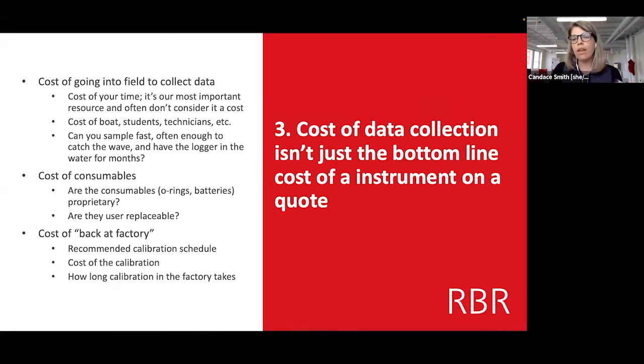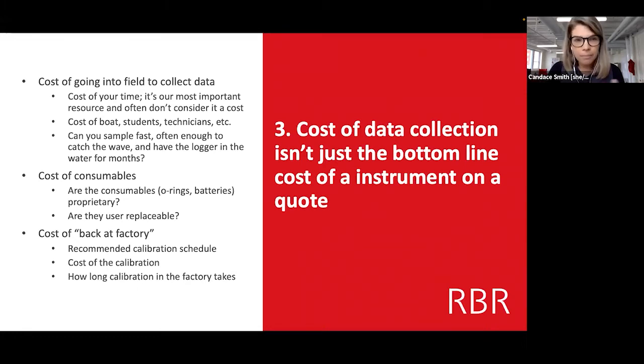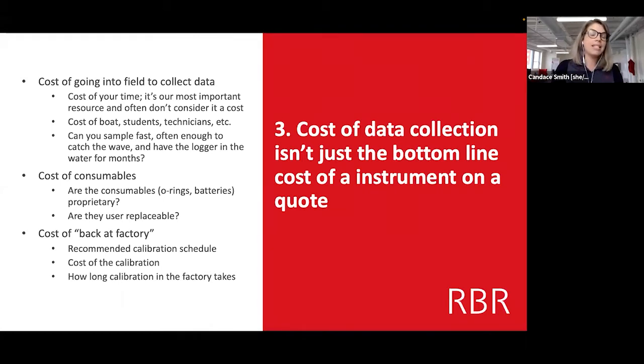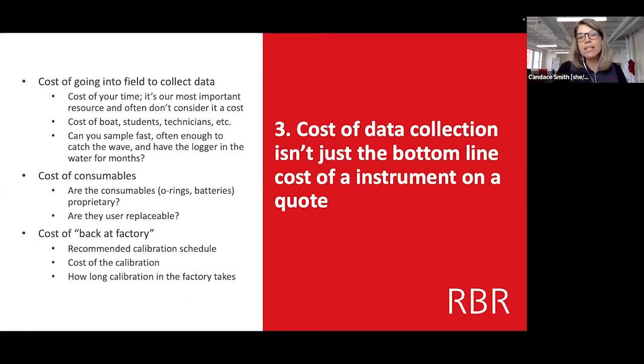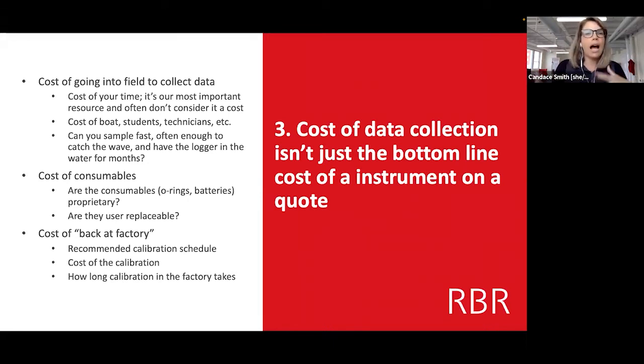There's the cost of consumables — the things you use up on an instrument. Are they proprietary, must they be replaced by the manufacturer, can the user do it, are they easy to find? And there's also this back-at-factory cost: how often are manufacturers recommending calibration, what is the actual cost, and when it's back at the manufacturer, how long is it there? What's the cost of you not having that instrument in the water? If you're doing a two-year deployment and need calibration at the year point, is it going to be out of the water for three or six months?